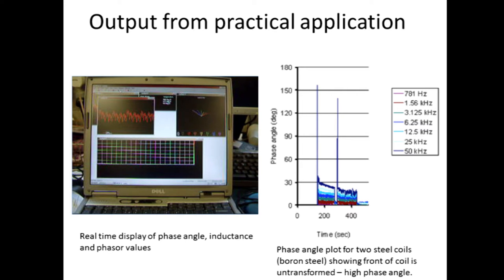Coming back to the idea of different magnetic and sensor signals, there's analytical work done by our collaborators at Manchester showing that if we take a particular aspect — the phase angle — you can make it relatively insensitive to lift-off and target geometry. Provided you've got some hot steel there, your signal won't change because of different amounts of steel present — you're just looking at the transformation characteristics. This is where the fundamental work and modelling fits alongside.